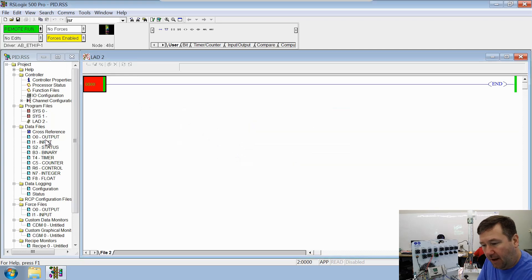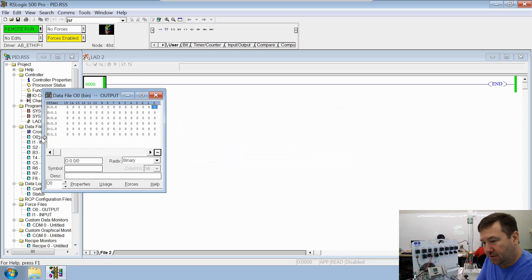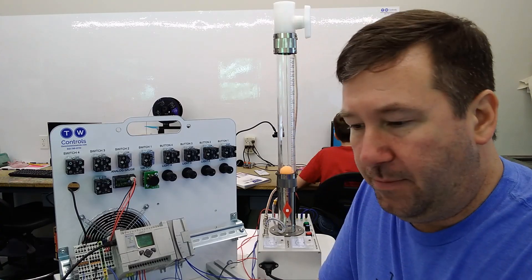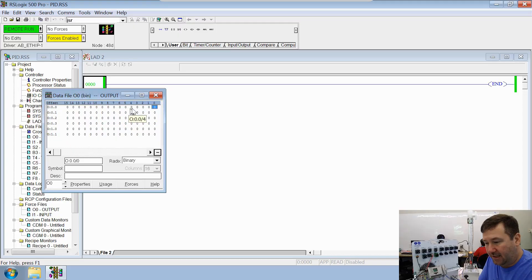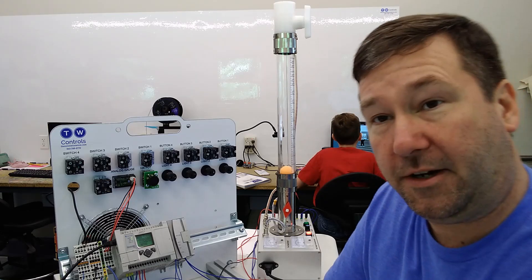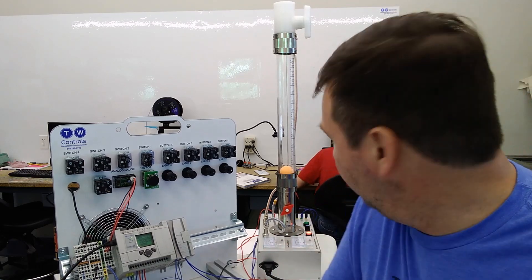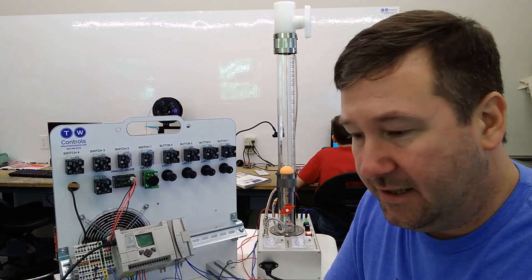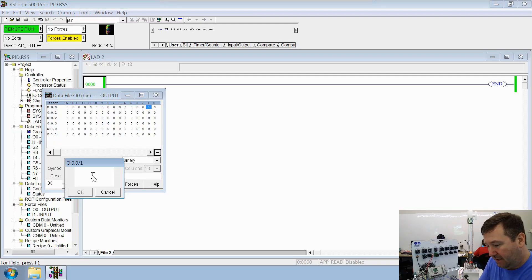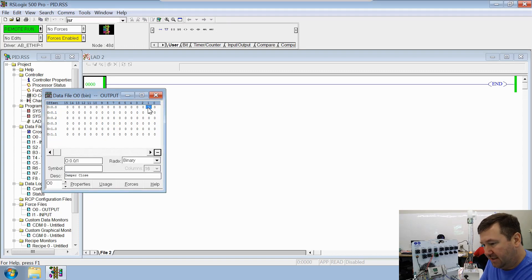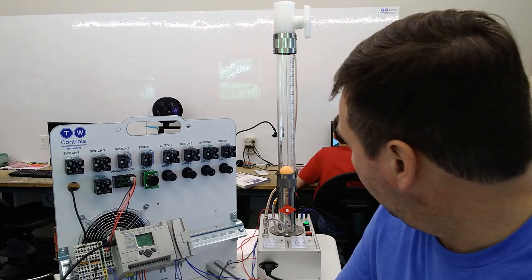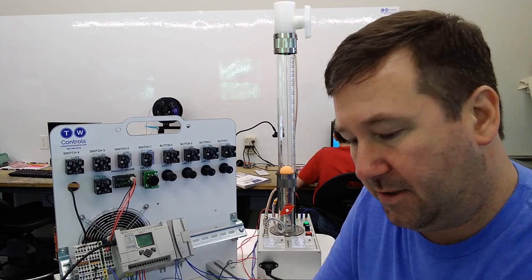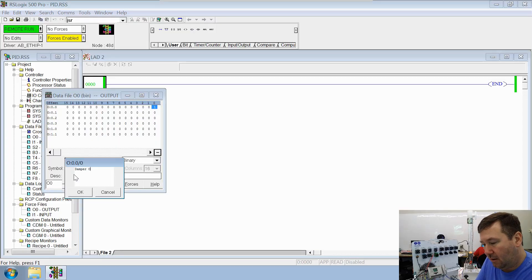Let's open up our output data files, and we're going to test our damper control first. So output zero should be open, which it is open right now. So let's try changing output one to a one. Okay, and we can see by the indicator there, it is closing. So this is going to be our damper close. And we'll put a zero back in that one. And then output zero, if we put a one in it, yes, that is going to open our damper up. So that will be damper open.